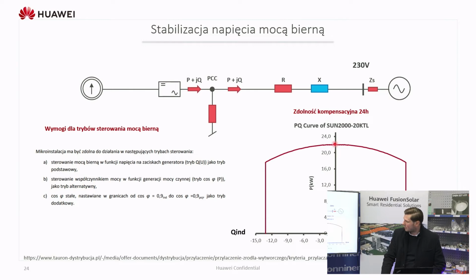So here is the point where we are working usually: maximum output active power and zero reactive power. But the inverter can work, for example, here, with that much reactive power and that much active power. It's not a problem for the inverter. Most of them have a characteristic like this.